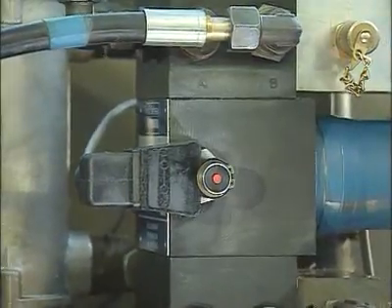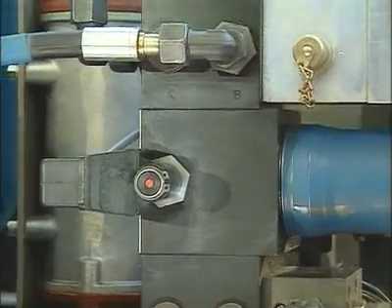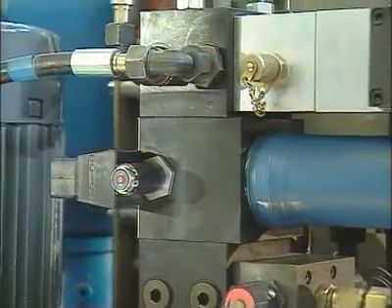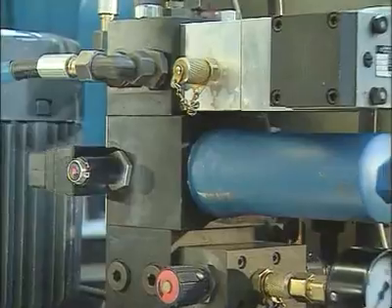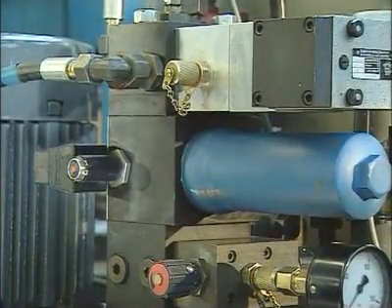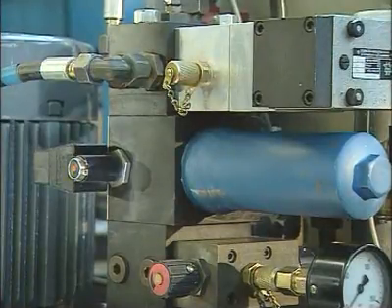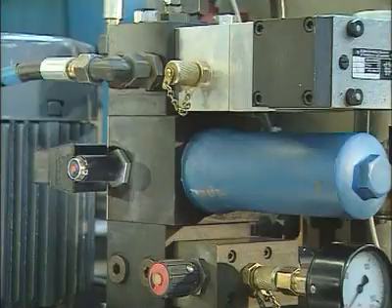The differential pressure switch is a special type of pressure switch. One application is the monitoring of the contamination of an oil filter in a hydraulic pressure line. This is done by tapping into the lines upstream and downstream of the filter. The pressure differential is a measure for the contamination of the filter, independent of the effective pressure level.